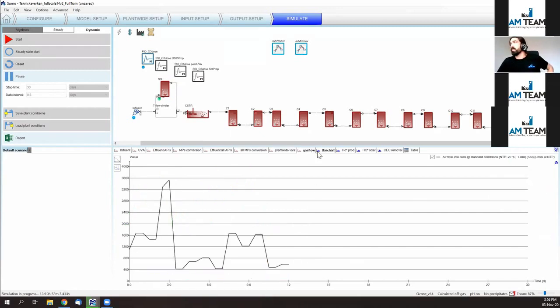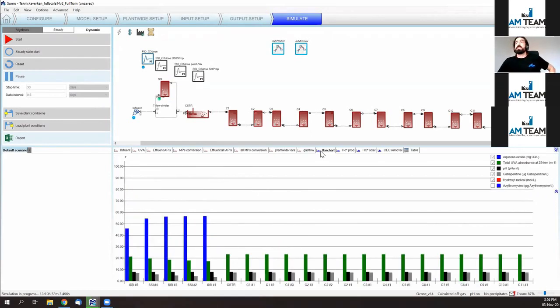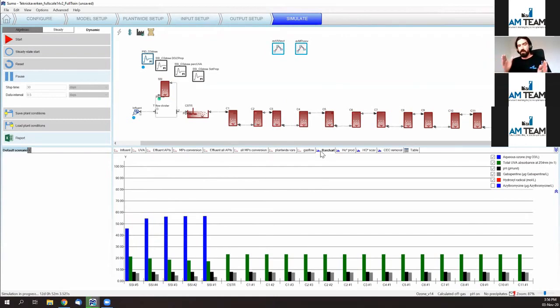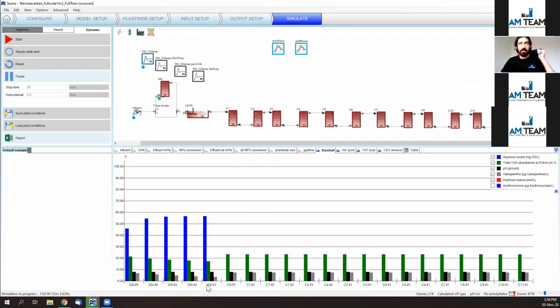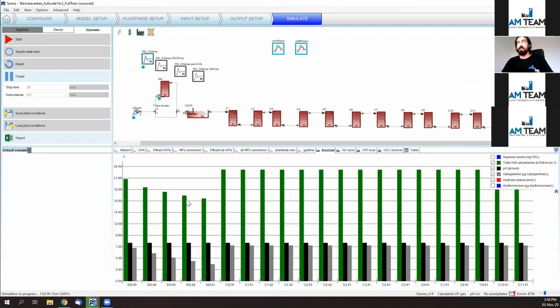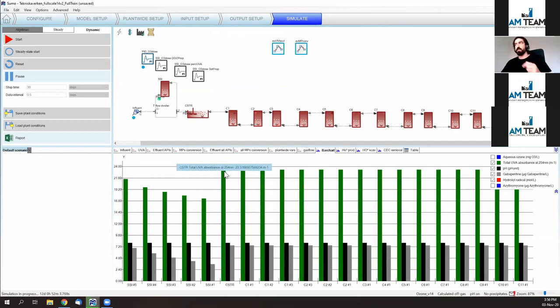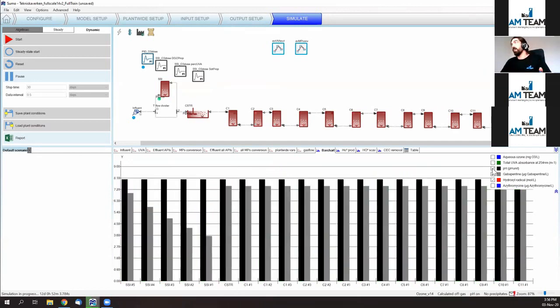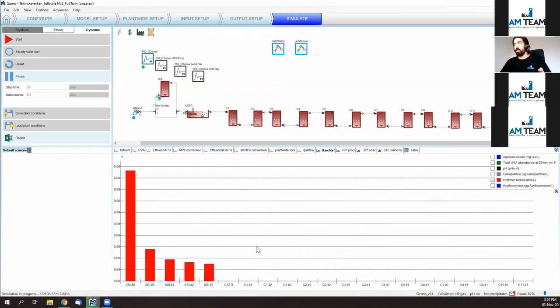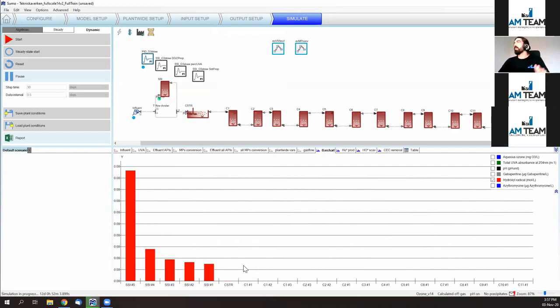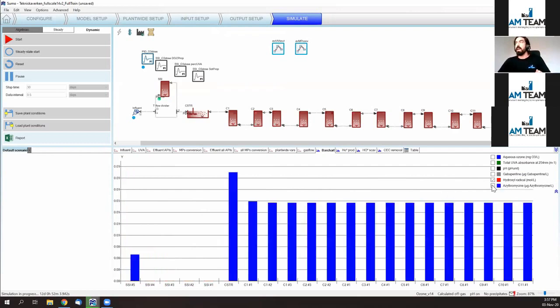All right, here's some gas flow, that's some process parameters. What is interesting to look at is a picture in an instance, in a single moment of the concentrations along the installation. So what are the concentrations here and there about like ozone in the side stream, where you have high pressure and high-speed injection of your ozone. What is the concentration of UVA along the train in the side stream, and where you join again the mainstream. So you have an increase again of the concentration, but not only in also about pH and micropollutants, and nonetheless, also hydroxyl radicals. What is the local concentration of radicals? Where is that my radicals are produced the most, and where is that each micropollutant is depleted and to each extent.